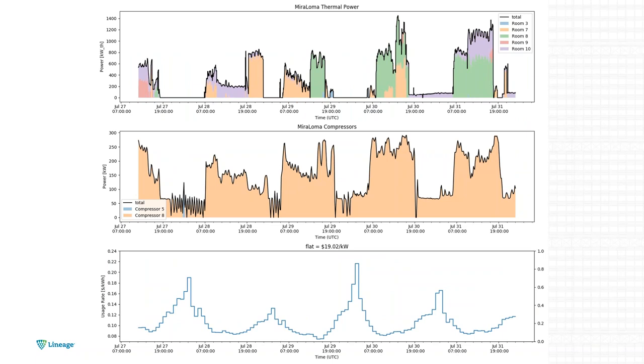Okay, here's the results. It actually works unbelievably well. On the top panel is the amount of heat being removed by the freezers, measured in thermal kilowatts. The bottom panel shows the prices on the real-time energy markets at this facility, which is on direct access. The middle panel is the power consumption from the refrigeration system, specifically the compressors, which I've highlighted here.